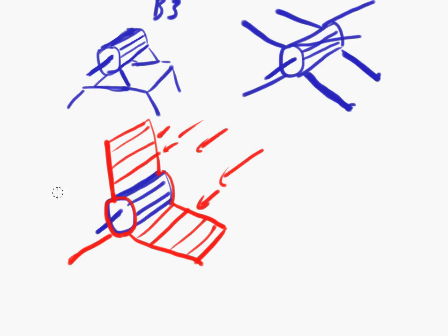Or the other way around, if air flows this way, then those vanes would clean up the air after that air leaves the impeller, and thus minimize the drag in this area. So that's an idea I haven't seen often. And the nice thing about this idea, you don't need those special B30 motors, which are more expensive. You just get a B3 motor, just take off its feet.